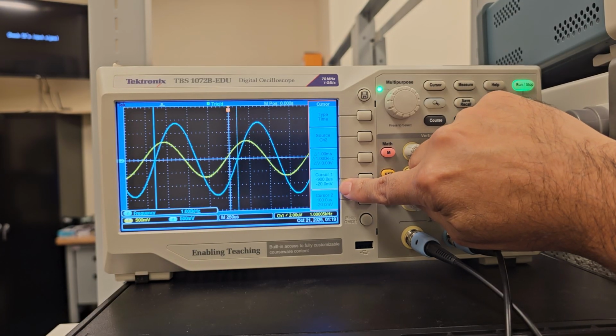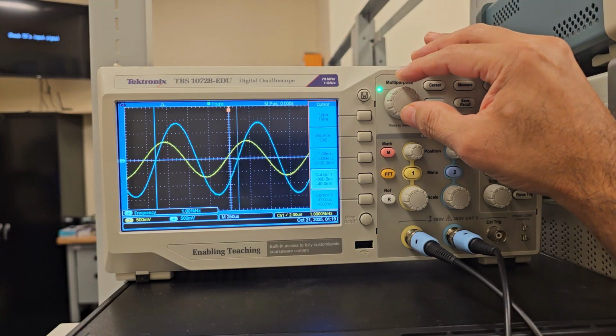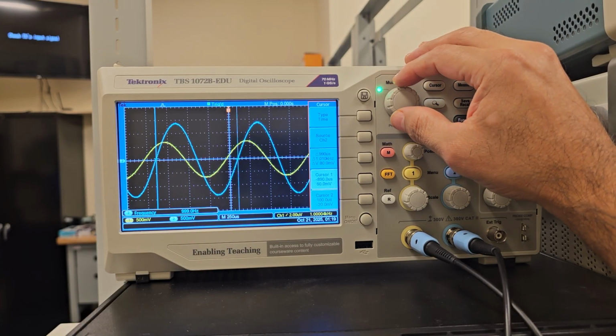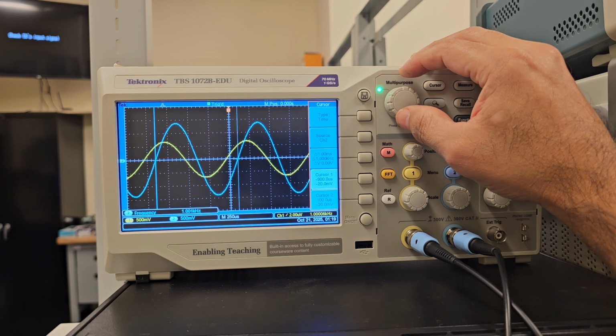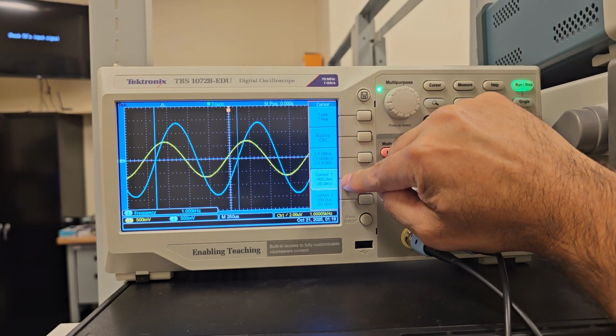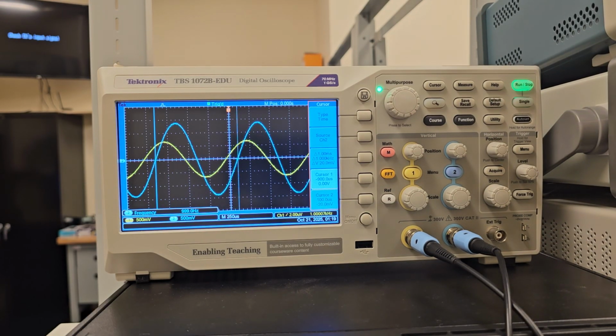900 microseconds, 20 millivolts. And I'm measuring the frequency, the period from here all the way to there. Now if I make it a little bit more, sorry, right there. I'm sorry, the measurement's up here. 1 kilohertz, 0 volts. That's cursor 1, that's cursor 2. Again, I keep doing this. All right. And I'm just going to keep the recording like this because I don't mind if I make an error here or there. It's good for you to see me do this and work my way through it. And every oscilloscope, you just got to get familiar with where the functions are at.